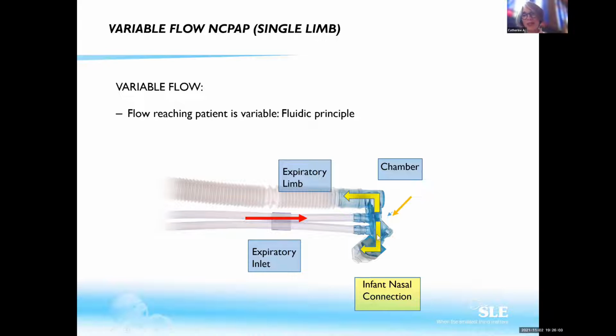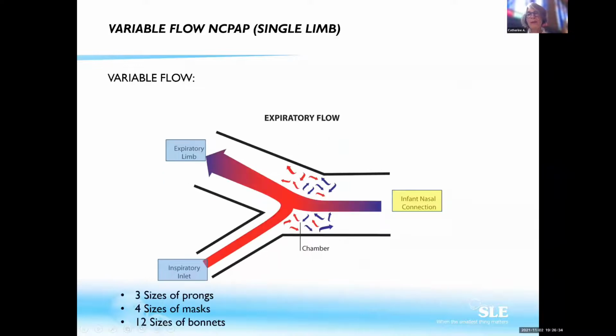The second point that is very nice is that whenever your patient is exhaling, of course, he will be exhaling against the flow. So you will see the pressure going up at the level of the interface. At that time, because the pressure is higher here, you will have more flow going to the exhalation. So the patient will be exhaling against a lower flow, against less work of breathing. So whenever you use a variable flow, you will see that your work of breathing will be decreased.